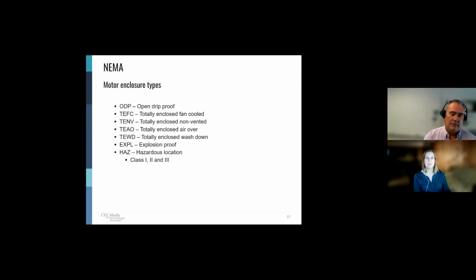We have non-vented in case we have an environment where we don't want particulates in the motor. Okay, we have totally enclosed air over. That's a slightly different version of the TENV. Totally enclosed washdown. Obviously, that's for a very wet environment, like a washdown room at a food processing plant type of thing. Explosion proof. You're doing a grain elevator, a flour storage bin, so on and so forth. You don't want anything getting out or in. And then if we go into hazardous locations, we have class 1, 2, and 3. Again, more things that we need to think about as we're selecting a motor.